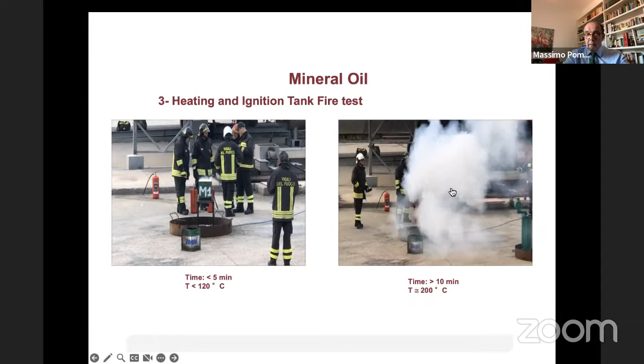So we are heating the transformer. After 5 minutes, we reach a temperature of 120 degrees. And on the other side, the natural ester, nothing happened. This is mineral oil. Then the mineral oil started to vaporize or to burn, producing a lot of vapor.